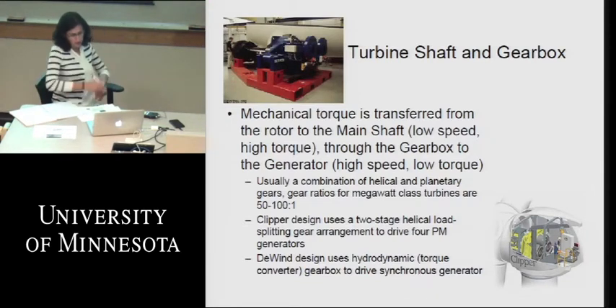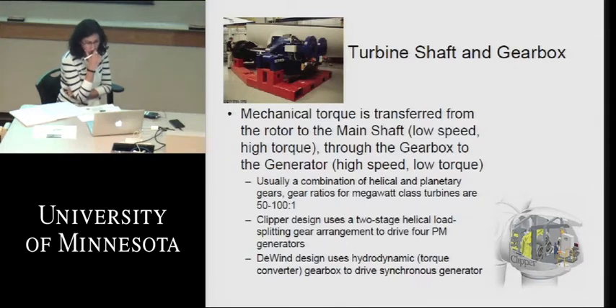And the last bullet there, DeWind is a German company, and they use a fluid clutch, essentially a hydrodynamic torque converter. That way they can use a synchronous generator with a fixed synchronous speed of its excitation, and in doing so it changes the slip characteristic. Instead of doing it electrically, like most of the other manufacturers do, and certainly how Vestas does it, where we use electric slip, they control hydraulic slip to match up the synchronous speed of the generator with the speed that you're getting from the actual rotor of the wind turbine.